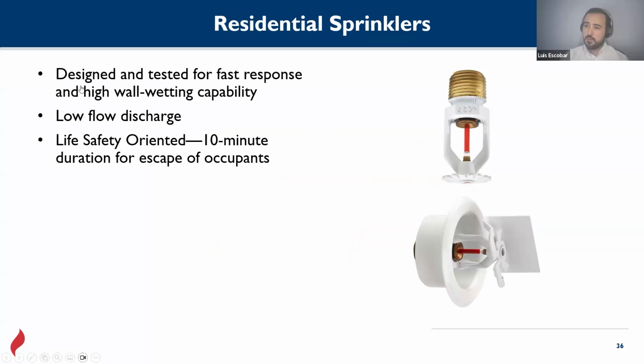Residential sprinklers: NFPA 13 by itself doesn't provide guidance for residential. That's why we go to 13R or 13D. These sprinklers are very small. They don't release too much water. And one of the main features of these residential systems is that, depending on the jurisdiction, sometimes we can use non-metallic piping.